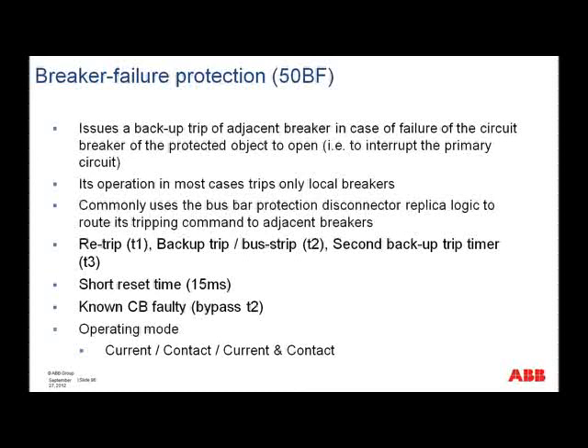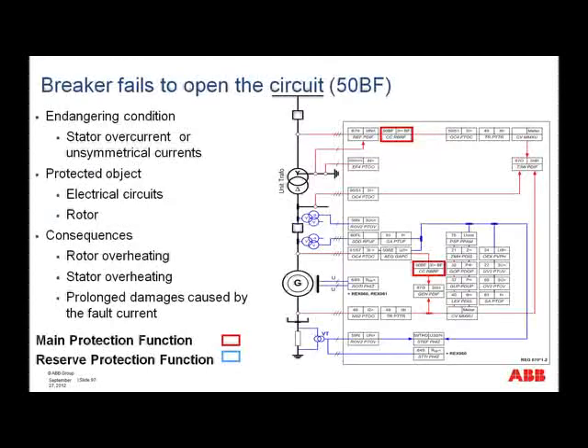It's possible to get re-trip functionality. The backup or bus trip, okay, the trip comes after the normal T2, but depending on the number of breakers that actually have to be tripped, and maybe this is not applicable for a power plant, but if that's a large number, then maybe you want to trip them in batches, and so you have the option of the first batch being tripped after T2, and then starting from T2, there's a T3 timer that would trip the remainder. So here you can see we have the overcurrent protection, and there are two of them, one for the generator breaker, one for the breaker on the HV side of the transformer, and each of them would get initiated or started by protection that is tripping the breaker they are assigned to.